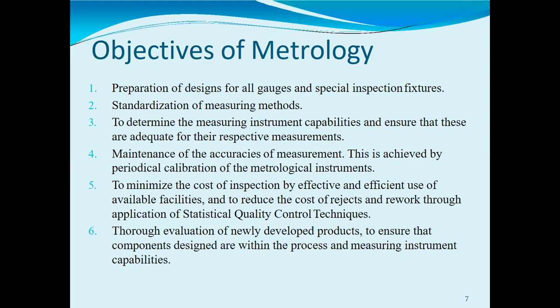maintain the accuracy of the instrument by doing proper calibration every month, and minimize the cost of inspection by handling the instrument efficiently and minimizing the number of rejects due to unwanted failure issues. This can be done using statistical quality control techniques. With the help of statistical quality control techniques, we can define the population size or batch size by considering a lot. So take a few random samples from the whole lot and do the quantitative analysis.